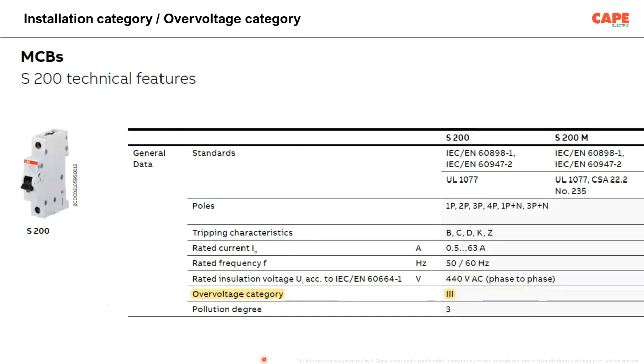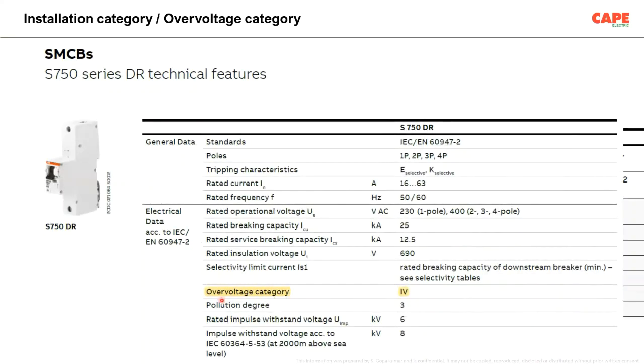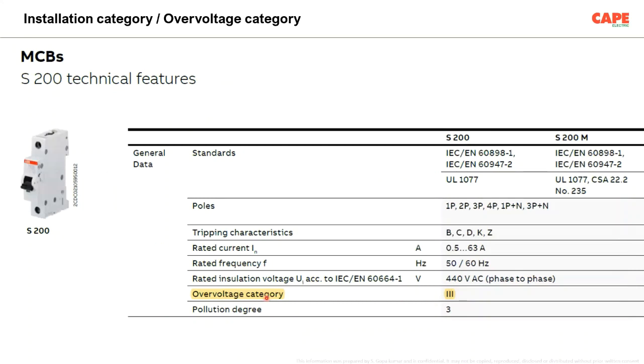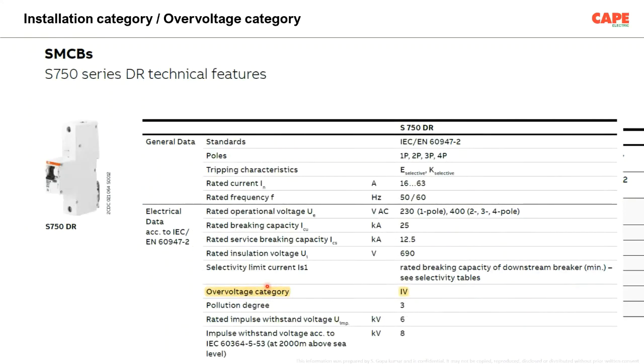Similarly, this is an MCB, overvoltage category 3. Another MCB from the same manufacturer, overvoltage category 4. Very simple to understand. The first MCB, overvoltage category 3, you cannot use at the point of commencement of supply. If you wanted to use an MCB at the point of commencement of supply, you have to use this particular model, which is, of course, even a bigger one.